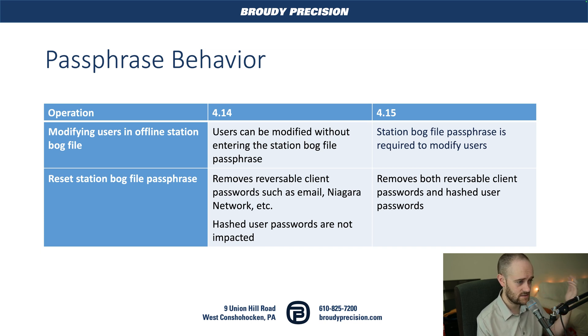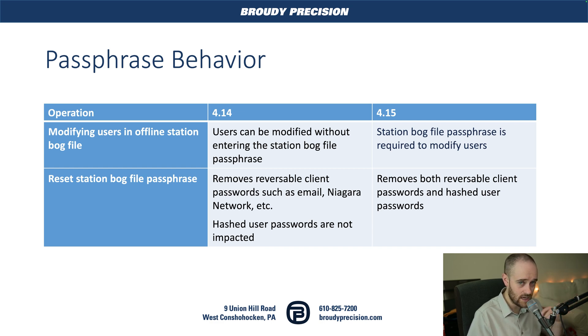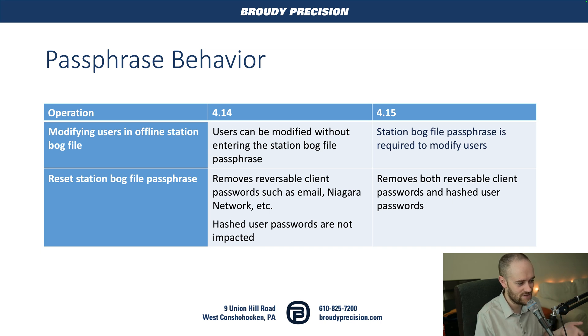In 4.15, this changes. A station bog file passphrase is now required in order to modify users. And to facilitate this, when you reset your passphrase, your passwords for your reversible clients — email, Niagara network — and your hashed user passwords both get reset and removed. Do not pass go, they're gone. So now let's jump into Niagara and look at what that passphrase dialog box looks like and see how it actually removes the users.